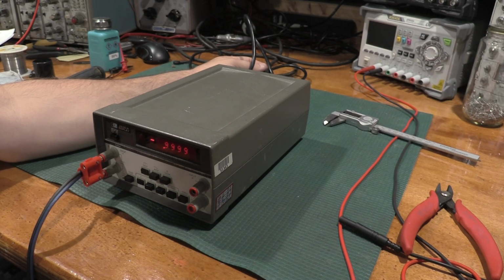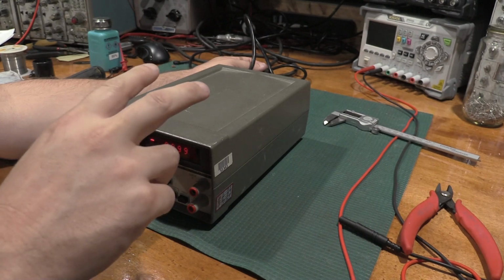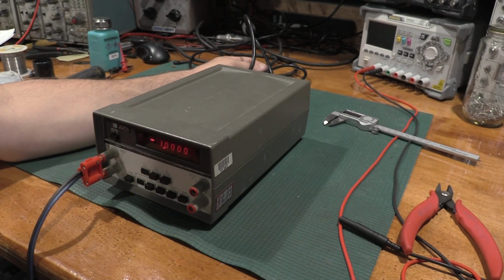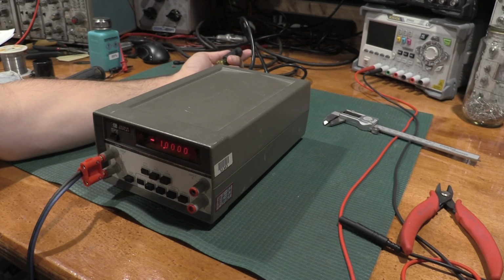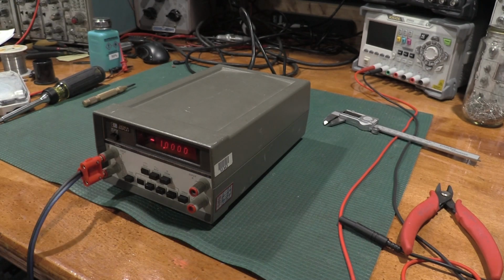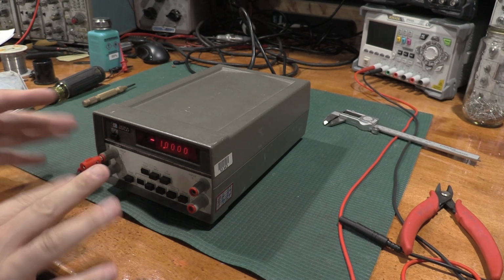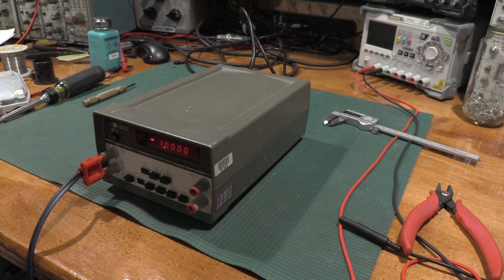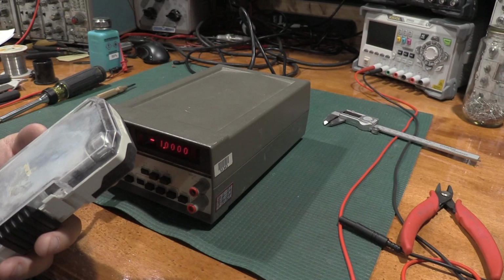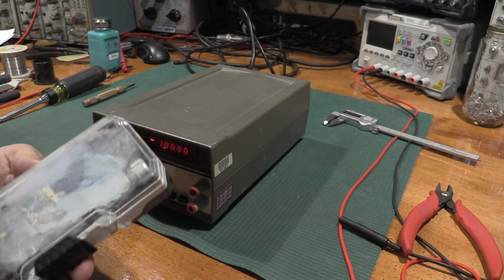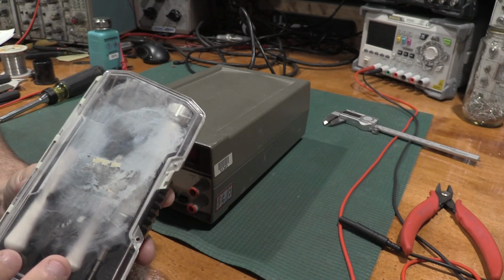now I'm trying to adjust it this way without putting too much lateral load on the potentiometer, because that can actually skew the reading. So I'm not really pushing on the screwdriver, it's just resting on my finger. And we'll pull the screwdriver away, and there we go. All kinds of weird and interesting things happen when you're doing an alignment and a calibration to get the most accurate results. Just waving my hands around here will cause the reading to jump around a little bit. That's normal.